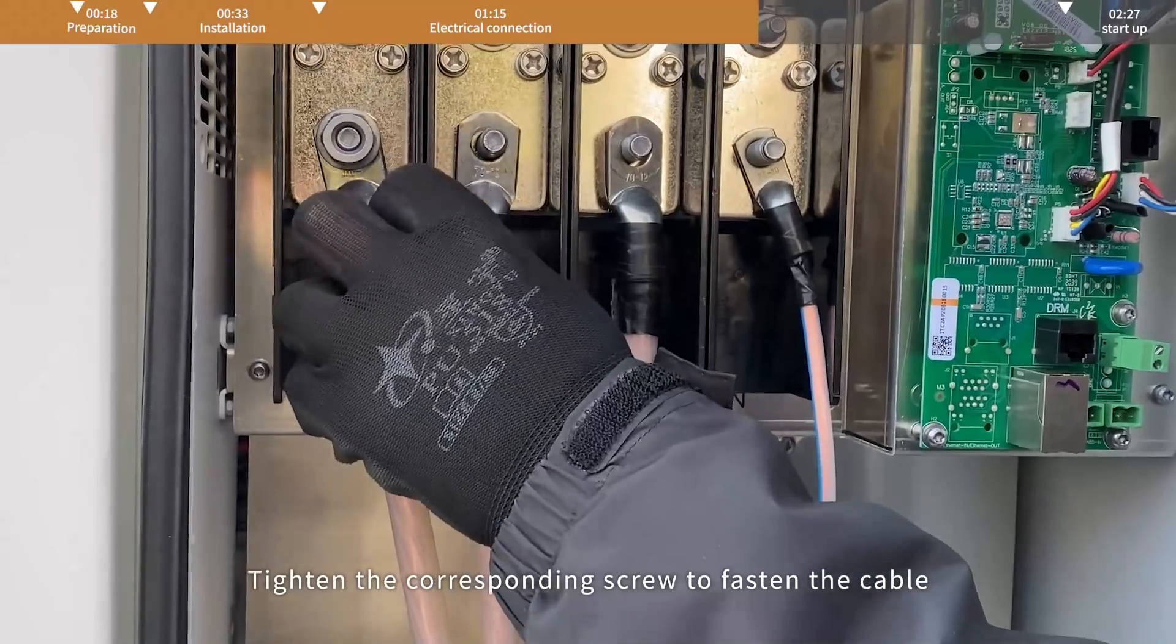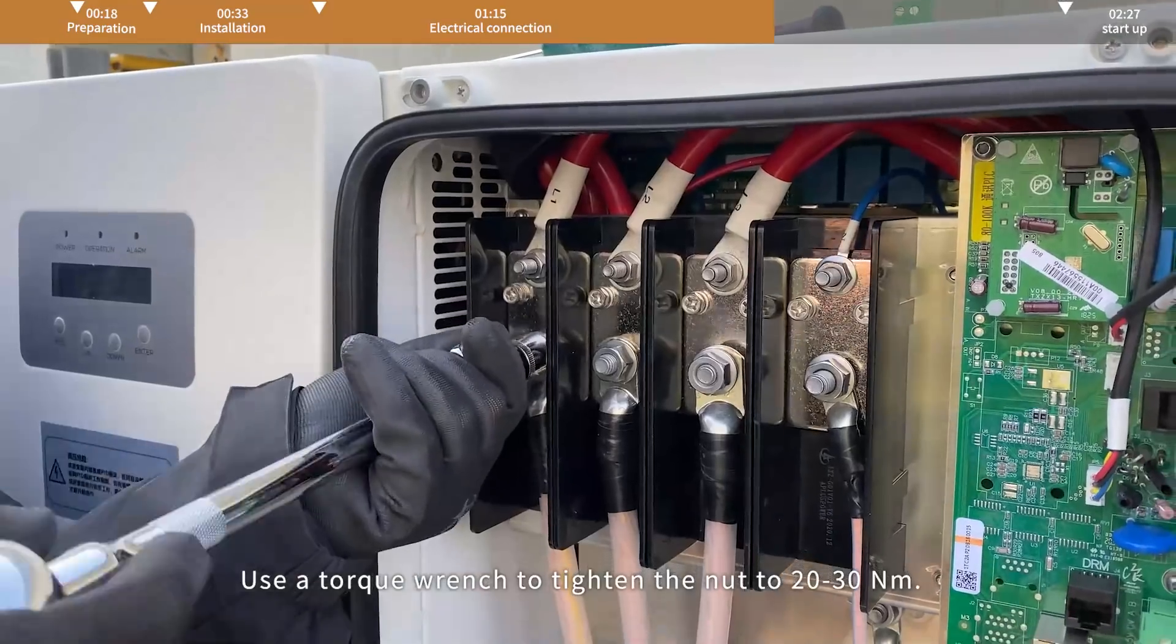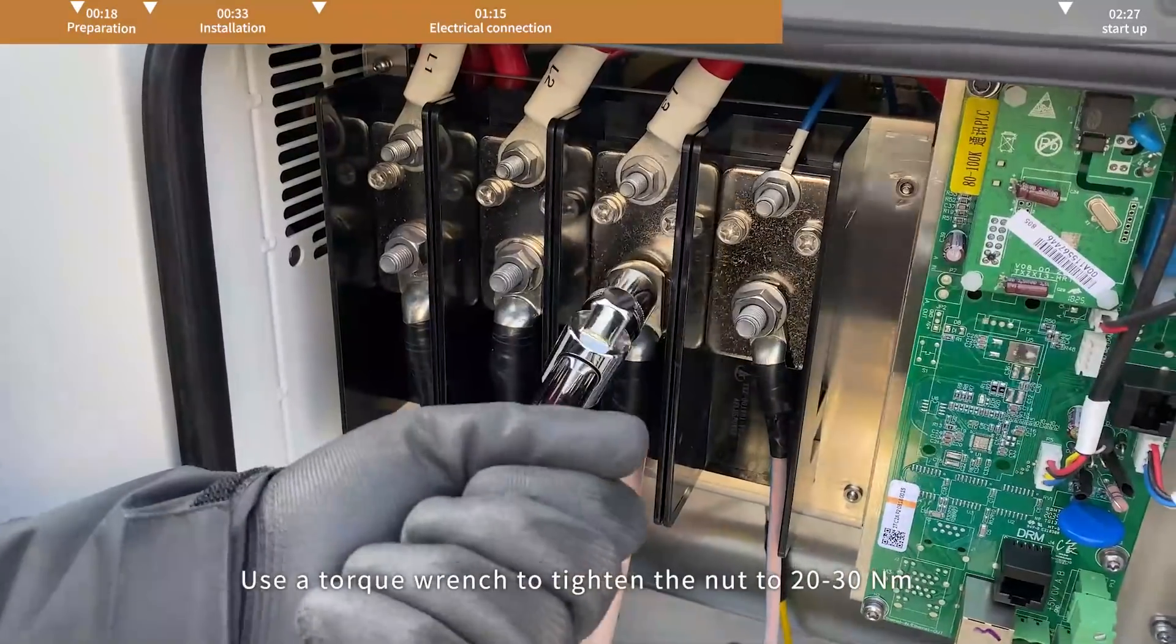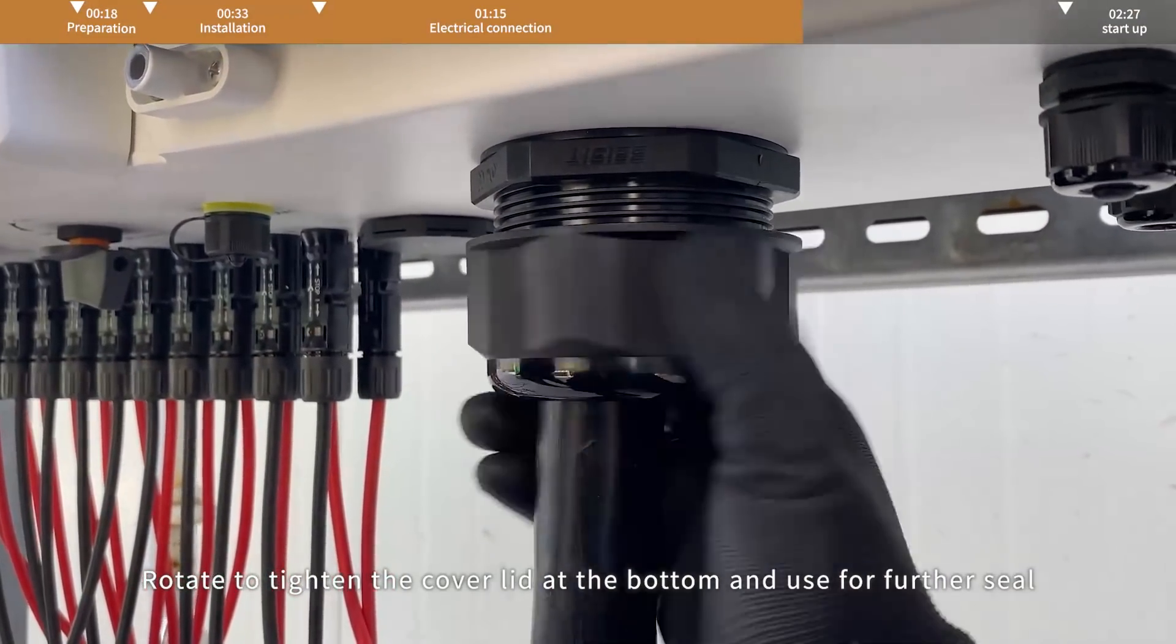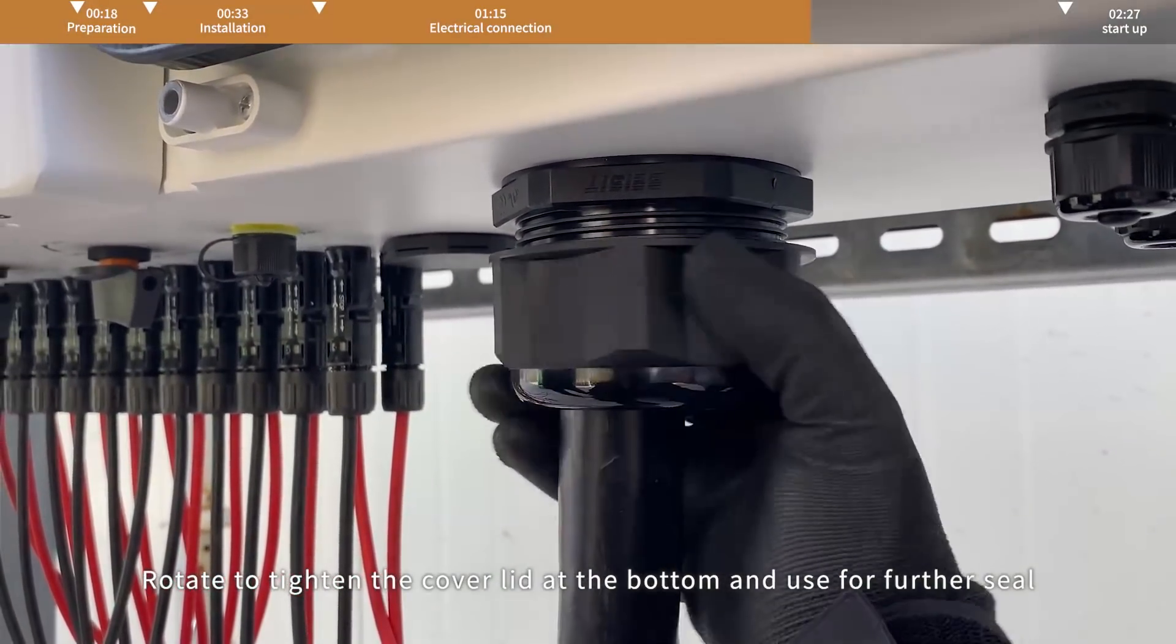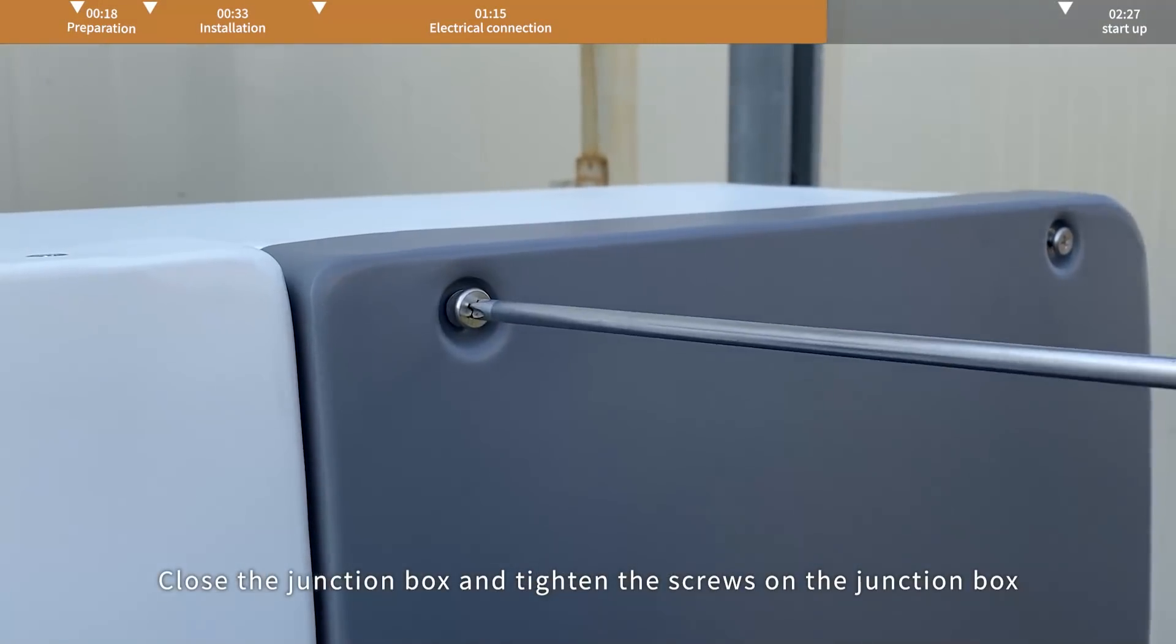Tighten the corresponding screw to fasten the cable. Use a torque wrench to tighten the nut to 20 to 30 Nm. Rotate to tighten the cover lid at the bottom for further seal. Close the junction box and tighten the screws on the junction box.